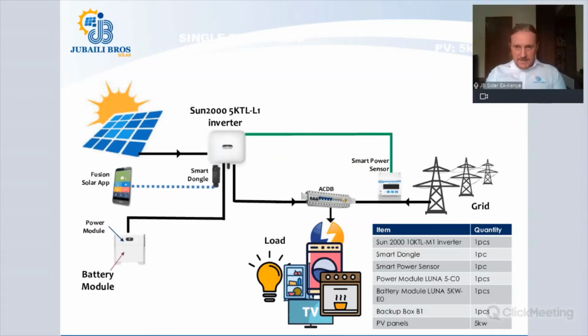Okay, so now let's look at some examples here. Some of that writing is white and it can't be seen easily. But this scenario here is a single phase scenario. Single phase grid tied, okay? So there, almost in the center, we have the inverter, the Sun 2000 5 KTL L1 inverter. And you can see the panels are there. In this scenario, we have 6 kilowatts of panels because it's a 5 kilowatt inverter. So we've used a DC to AC ratio of like 1.2. You can see the dongle there. The dongle is included in the box with the inverter, so you don't have to buy it separately, but it is the communication device that allows you to connect to the app.